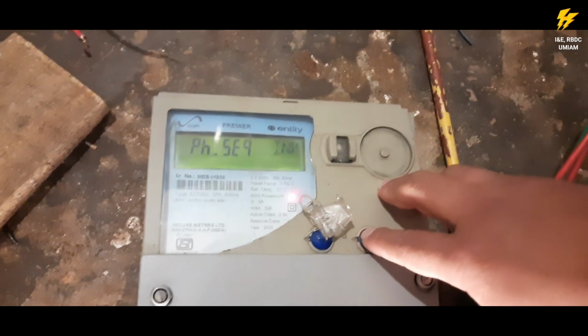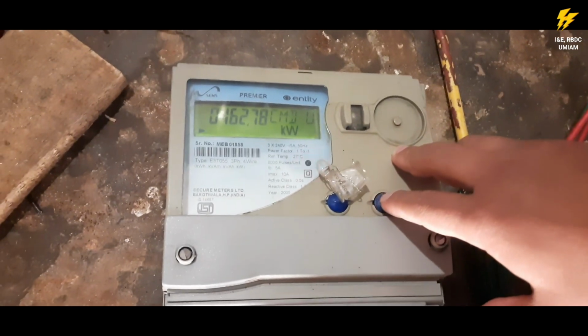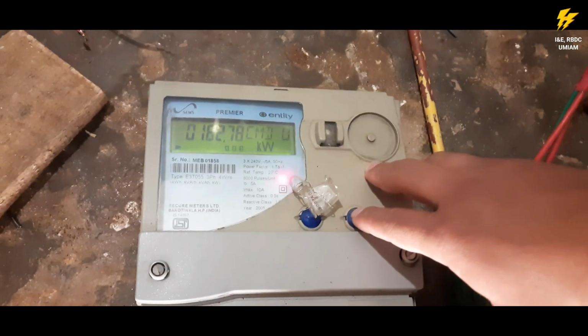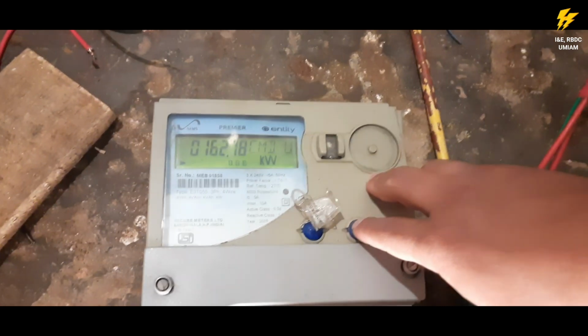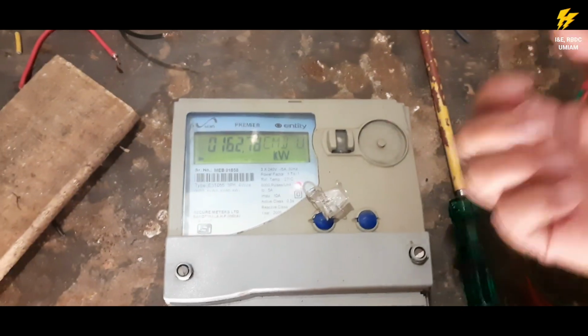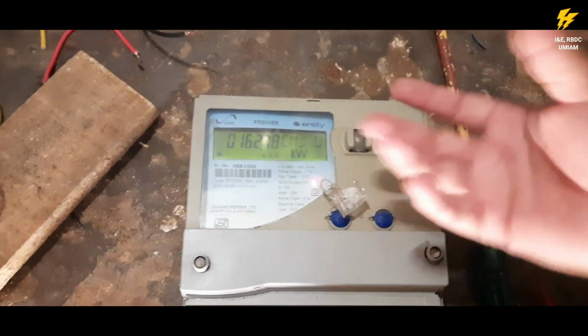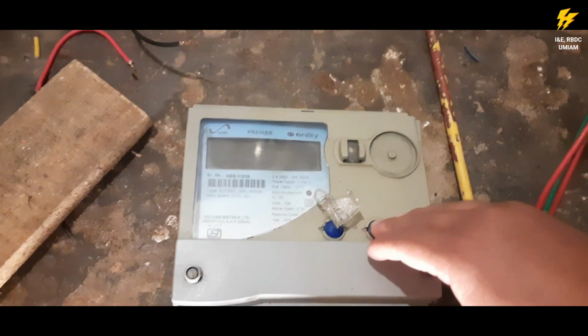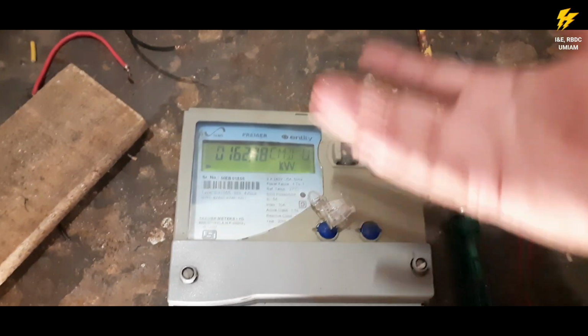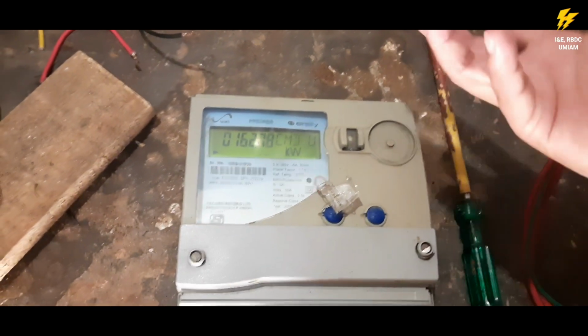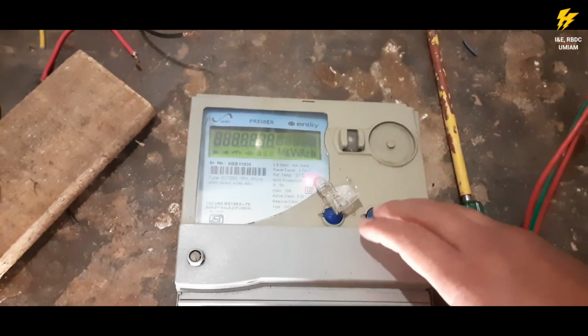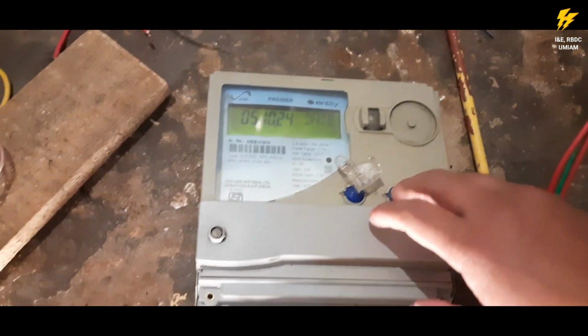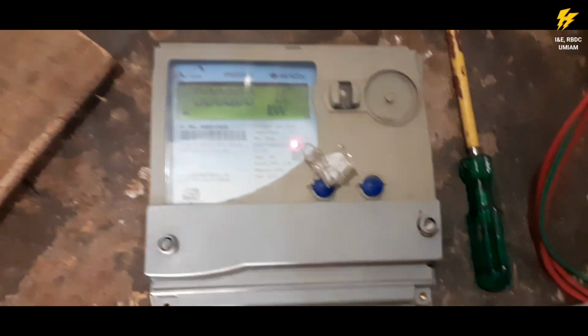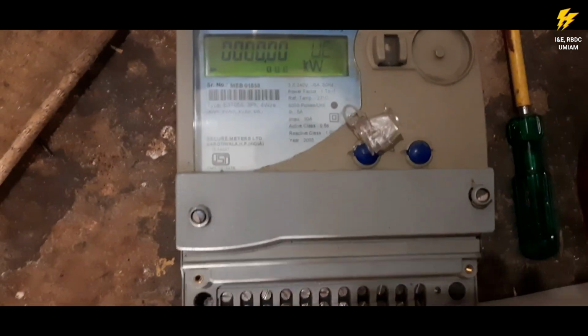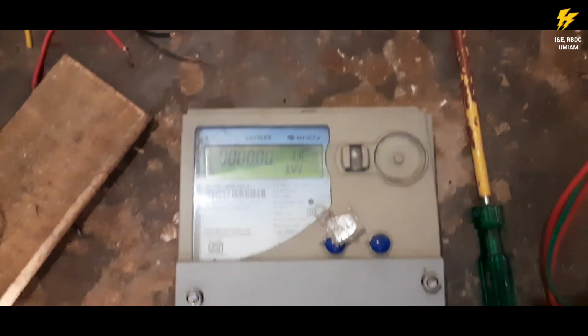Phase sequence inverse. In this, this is the CMD, cumulative maximum demand, 162.676. We should not take this for billing purposes. This is just to understand, like if somebody has reset the maximum demand. This is not to be taken for billing purposes, but it has been a mistake for the utility. Sometimes we take this and the bill shoots up. Okay, so this is how you do it. And the advantage of this meter is that even with the absence of neutral voltage, you can still keep the meter on.